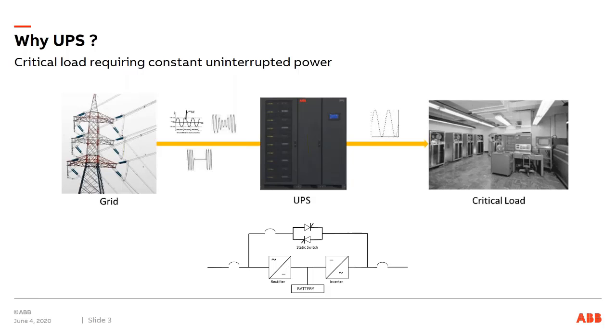And the UPS is constantly monitoring its own output, the stable 480 volts for the critical load. And if something happens so the inverter cannot maintain that, the inverter is a limited power source. If it's 100 kVA, it's a 100 kVA inverter. If there's an overload or a short circuit or similar downstream that exceeds what the inverter can handle, the voltage will drop. But the UPS control will see that, and it'll immediately transfer the load directly to utility power by firing the static switch. This happens in less than a quarter cycle, which is what still would be considered uninterrupted, not critical for the load at all.